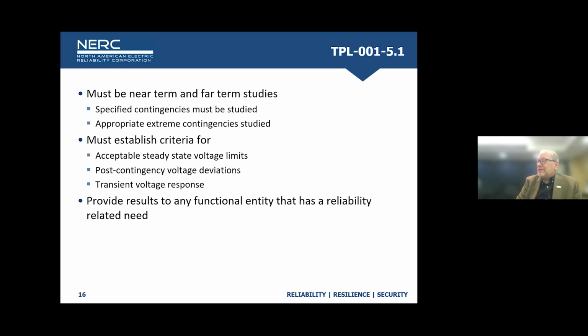There are specific contingencies that have to be studied, certainly N-1 generation outages, and then there are some extreme contingencies that are also listed that you need to study. For the N-1, you've got to stay within acceptable steady state voltage limits. You've got to stay between any post-contingency voltage deviations, and also have the transient voltage response that's specified there too.